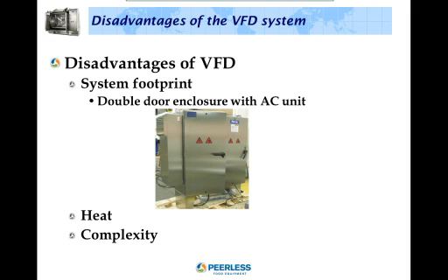Disadvantages of the VFD system. The system footprint. The electrical enclosure will be larger than a system using a two-speed starter of equal horsepower. This can be an issue as some bakeries do not have the available space for a bigger control enclosure. Heat. VFDs generate heat. This heat needs to be removed from the electrical enclosure to ensure the operation of the VFD. This can also reduce the life of the system and other control components. Due to the environment of a bakery, you may need to use an air conditioner to cool the enclosure.